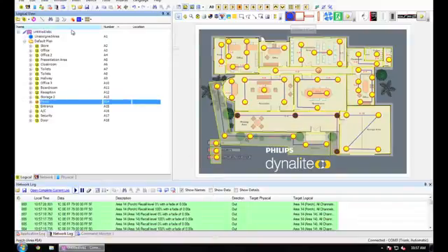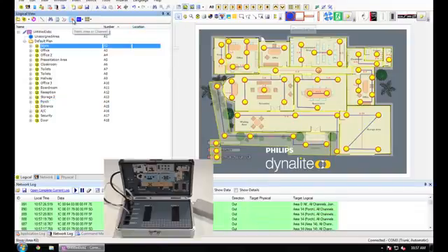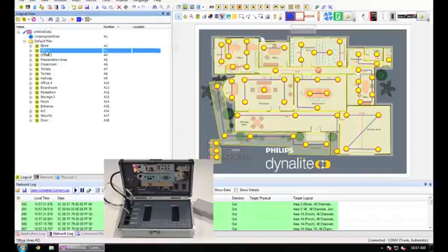The next thing that I want to check is that I have assigned all of the physical channels to the correct logical area. To do this, I can use the virtual panel on the toolbar to send an Area 0 preset 4 message to turn all of our areas off. I can see in my case that all of the lights are off now.